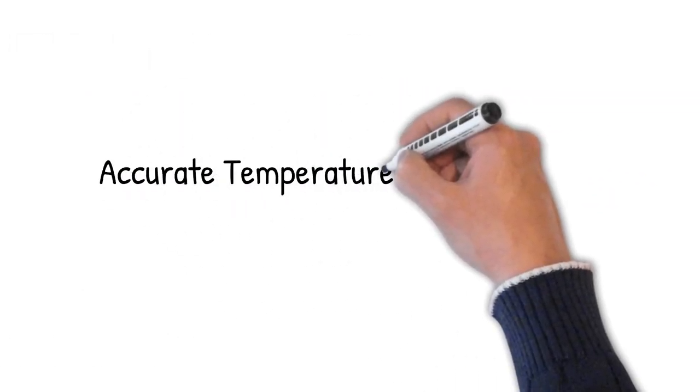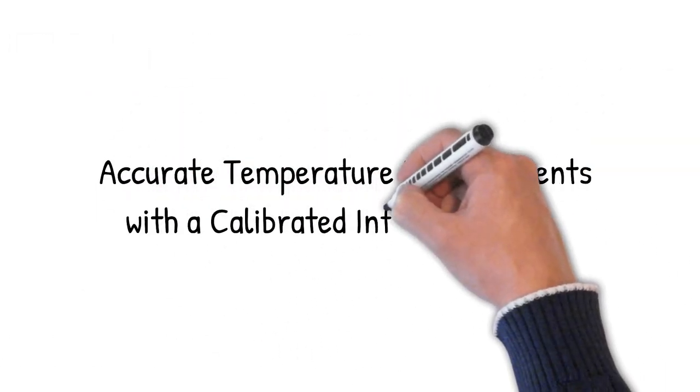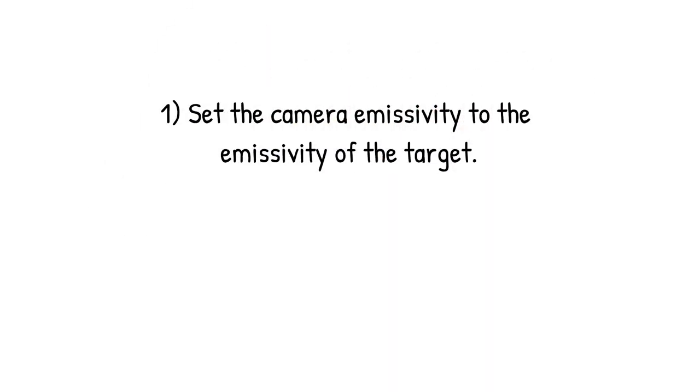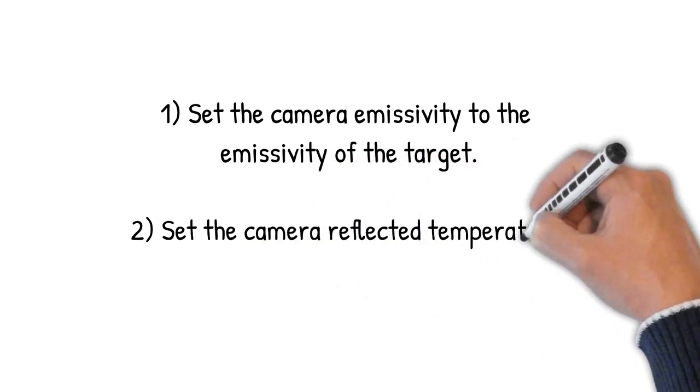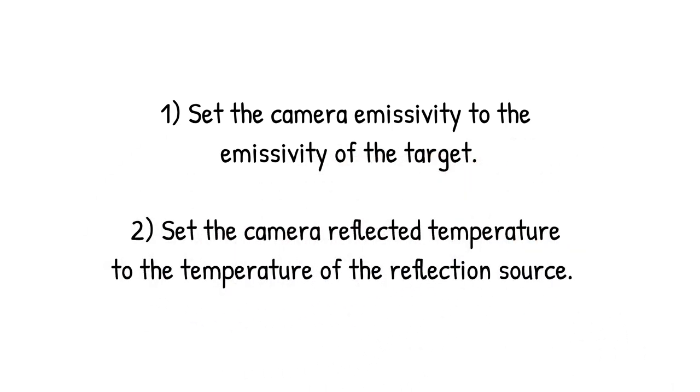To make accurate temperature measurements with a calibrated infrared camera, it is important to set the camera emissivity to the target and the camera's reflected temperature to the reflection source's temperature.